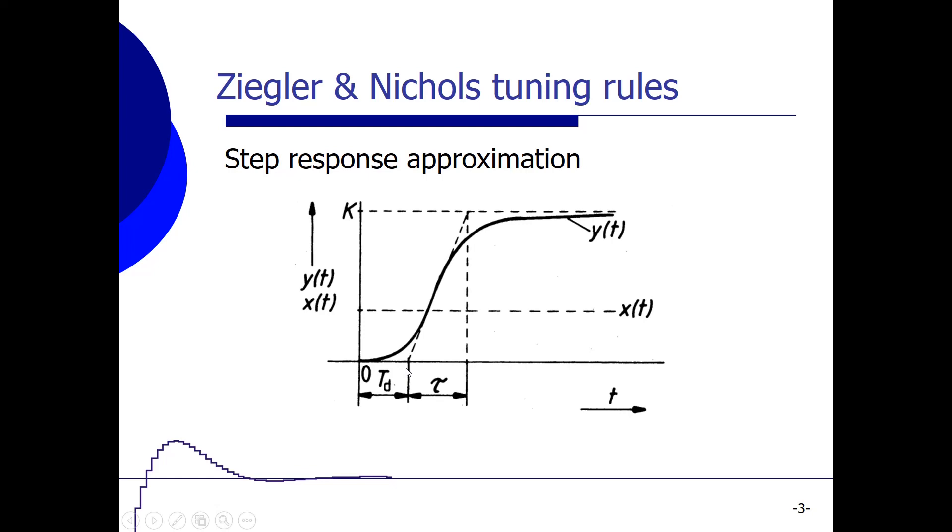So we can model our system by having a first order transfer function, and we add to that first order transfer function the transfer function of a delay. The delay time tau_d can be calculated using the intersection point of the tangent of y over here, this point, minus the starting point of our input step. And we can calculate the tau out of this signal by taking that same tangent over here and take the difference between the intersection point with the end value of y and the starting point over here. And then we have tau and the delay time tau_d.